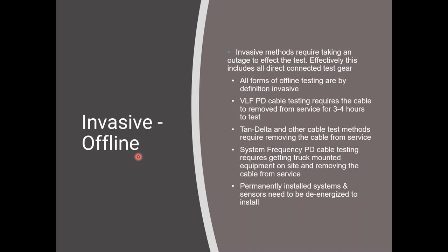Well, invasive or offline testing requires taking an outage to do the test. And effectively, this includes all direct connected test gear. So anything that you do a direct connection to, you have to take the system offline. You isolate the object that you're going to test. So if you're testing a bus bar, a circuit breaker section, or a cable, you've got to disconnect them from the power system, de-energize them, and totally disconnect them. By definition, having to disconnect the cables, it's invasive. That's where that terminology has come from.